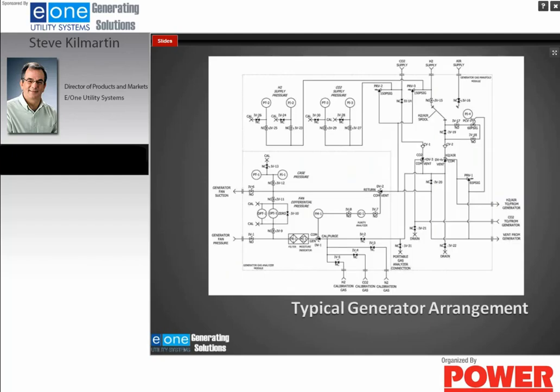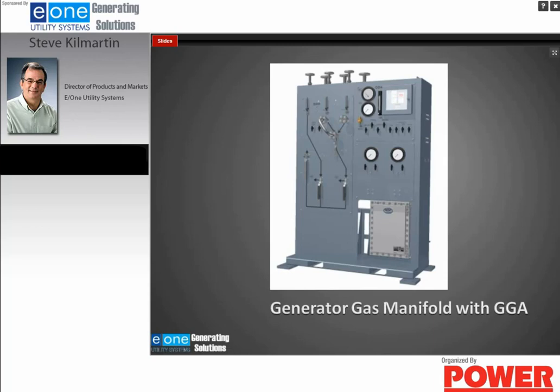One item that I would like to point out on this is that in the drawing, in the upper right-hand corner, you see what is called the hydrogen/air spool. The reason for this is that you don't want to have the ability to put air and hydrogen in a generator at the same time. So this spool is used to feed each of the gases so that it can only be in one position to either let air into the generator or put hydrogen into the generator. That piece is in the upper left-hand corner. It's a U piece of tubing. It's where the three flanges are, and you see that it can either be in one position or in the other position. One for air, one for hydrogen.